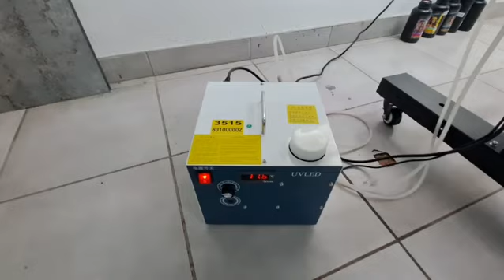To start off with, the chiller basically circulates water from the chiller to the lamp, then back to the chiller again. It circulates cold water to the lamp, brings back warm water, then cools it down, then sends it back to the UV lamp.